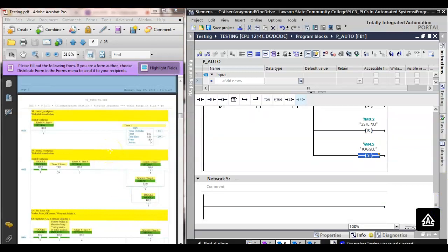Yes, it does on delay timer, so we'll see how that works. It's set for 1.5 seconds, which would be 1500 milliseconds, but we'll show you how we can actually enter it in seconds. Y'all okay there? Because we take 150, multiply it by 0.01, that would be 1.5 seconds. So all we got is a normally open, and then we got an on delay timer, which we've already put in our most used palette there.